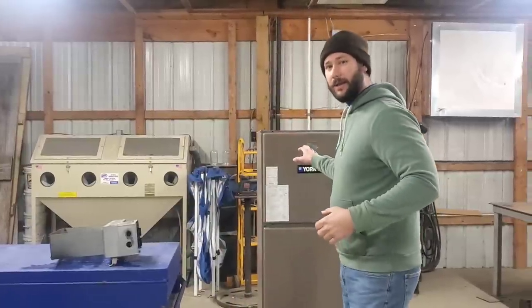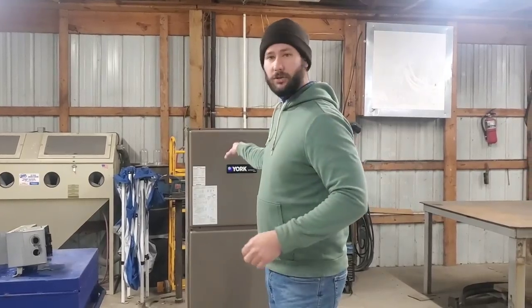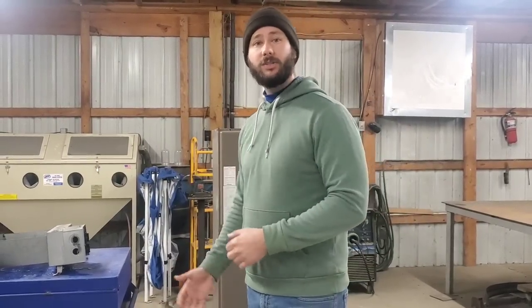When do you use the emergency heat? You use it when it's below 30 degrees. A normal air handler like this, which is a heat pump air handler — this is where the heat strips are contained. You usually use your emergency heat when it's below 30 or 20 degrees, because your heater is no longer capable of heating your home. The capacity is reduced when you have ice, snow, or freezing temperatures — you can no longer gain heat from the outside air.